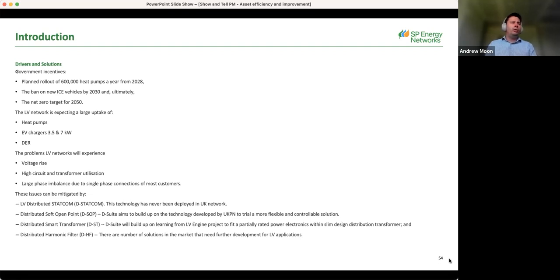They can do similar things to a certain extent, but the smart distribution transformer mainly enhances the functionality of a normal transformer by adding power electronic devices at either end, on the LV and HV side. A soft open point does something similar without the transformer present, but at the end of feeders and between two different networks, transferring power across two networks where it couldn't normally - improving load sharing across transformers, as I mentioned before.